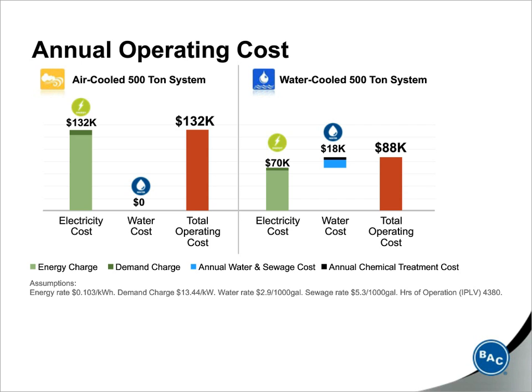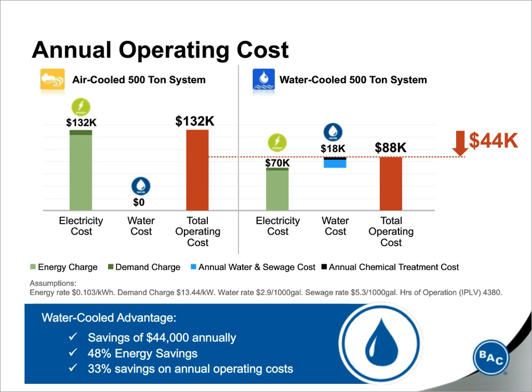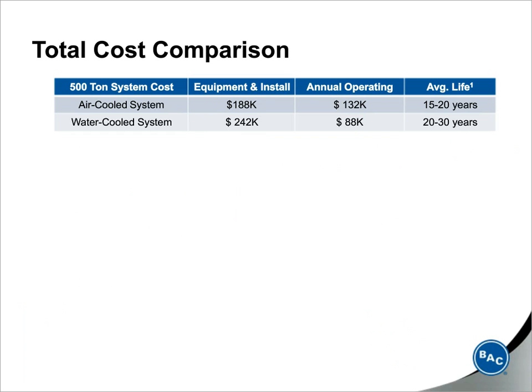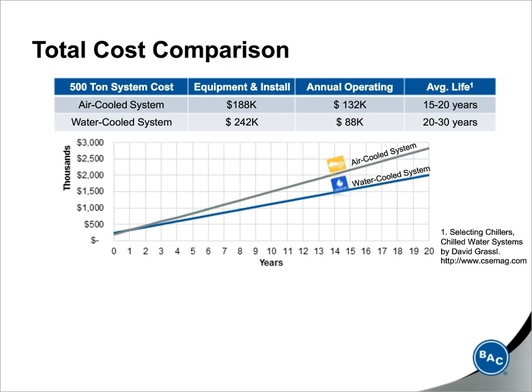This is $44,000 less per year in operating costs, and that basically brings down your energy consumption by 48%, and it offers 33% savings in annual operating costs. And remember, these are annual operating costs. So that said, let's actually expand this to lifetime costs. A water-cooled system, well, this chart actually shows the trajectory of air-cooled versus water-cooled systems.